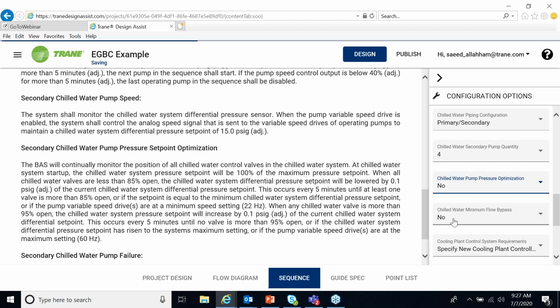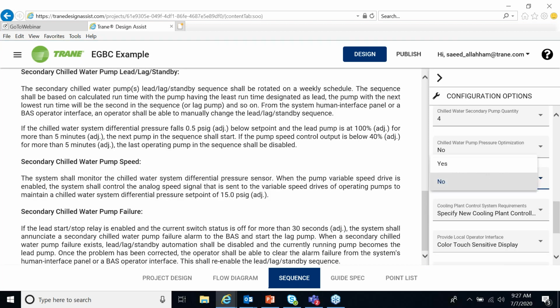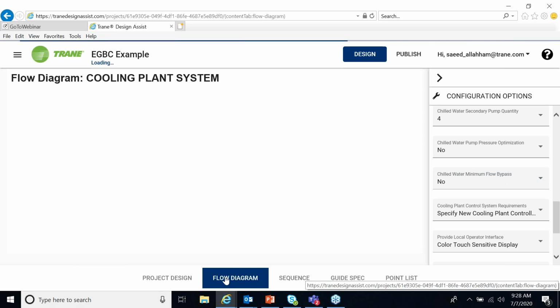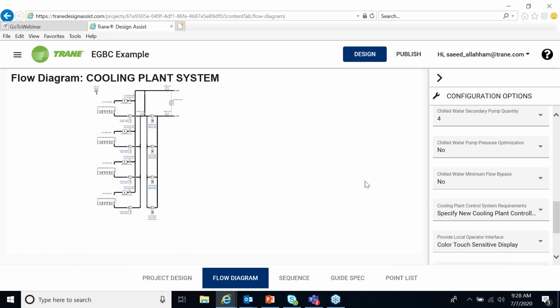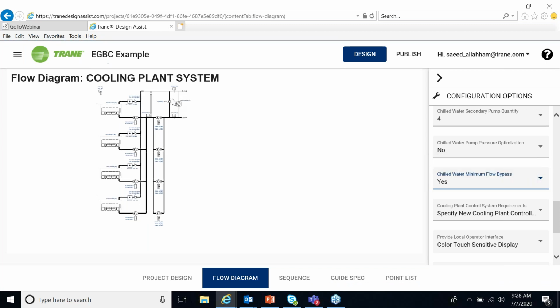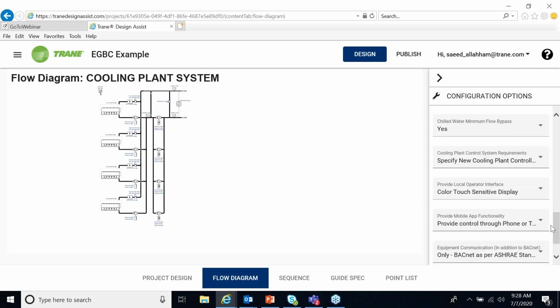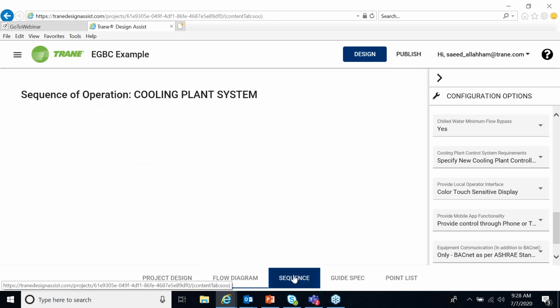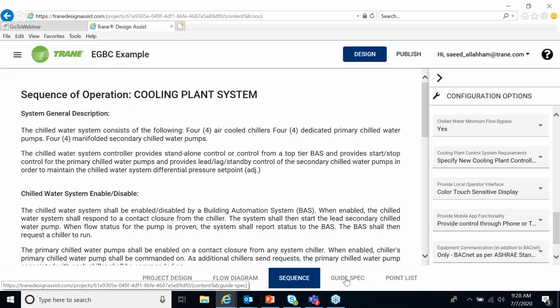Okay. Same here with, for example, minimum bypass. We selected here no. We go back to the flow diagram. Now, if I add minimum flow bypass diagram, you will see that it's adding now the minimum bypass flow to the system. So as we see here, it is intuitive. Based on the configuration that you make, all the changes that you make, it reflects immediately on the flow diagram and on the sequence of operation.